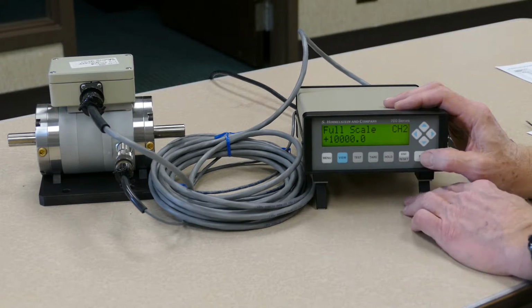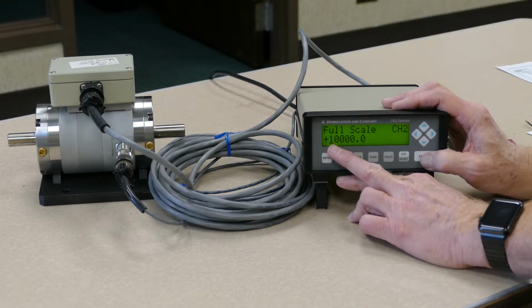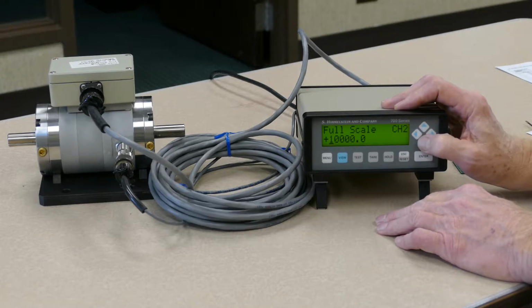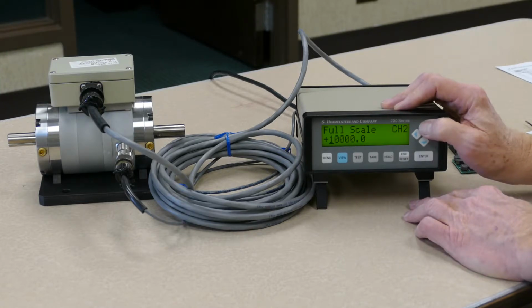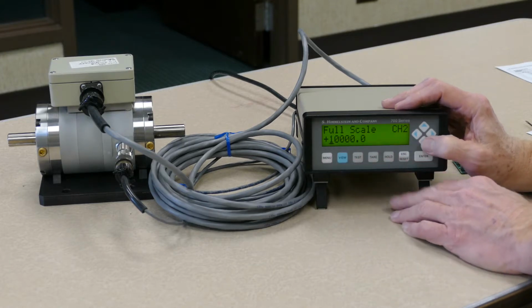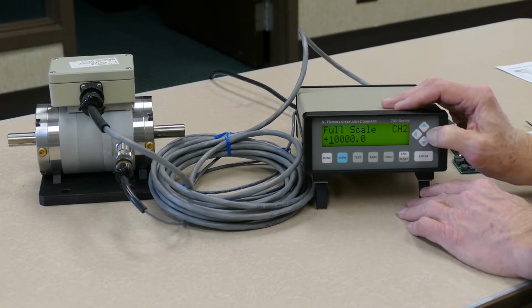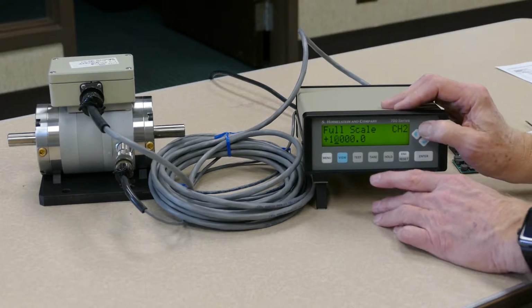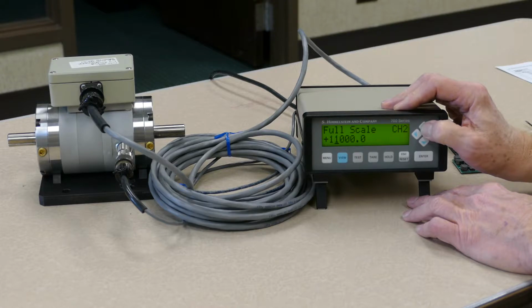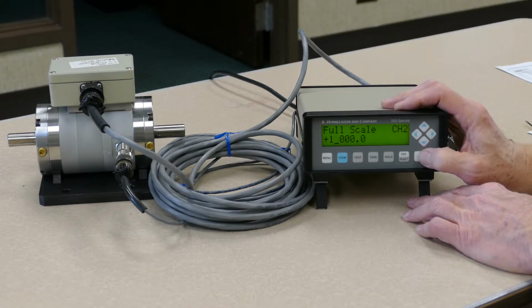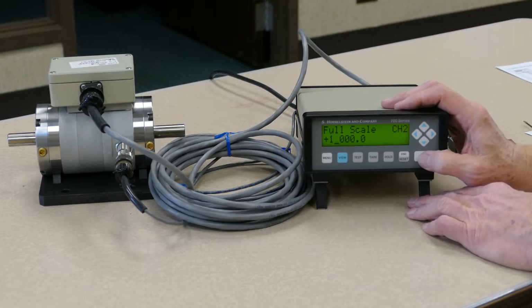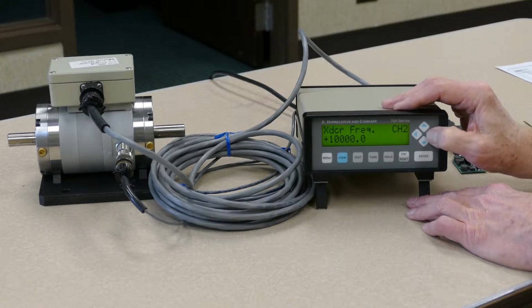In this particular case, the speed rating of this transducer is 15,000 RPM. We can set the full scale to be 15,000 RPM by hitting the enter key. And now we will display a cursor and a flashing number, and we can change the value of that number with the up and the down arrows. We want 15,000, so we'll leave that displayed as number 1. With the right arrow, we'll scroll to the next position, and now the 0 will be flashing, and with the up arrow we can change that 0 to be a 5, so that now the display reads 15,000 as the full scale. Press the enter key to accept that value and hit the right arrow to move to the next step.